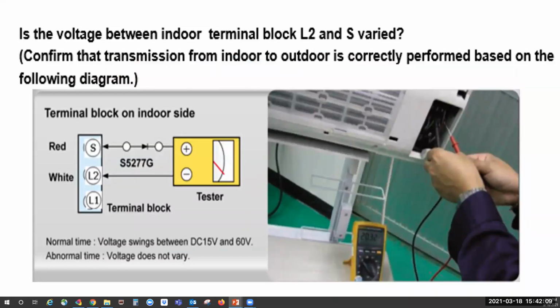Now, when you're checking for communication, you're checking DC volts between L2 and S. You want to have roughly 15 to 60 volts DC. It can fluctuate a little bit over and under, but we don't want it to go too far. It's a good idea to check this both indoors and outdoors.